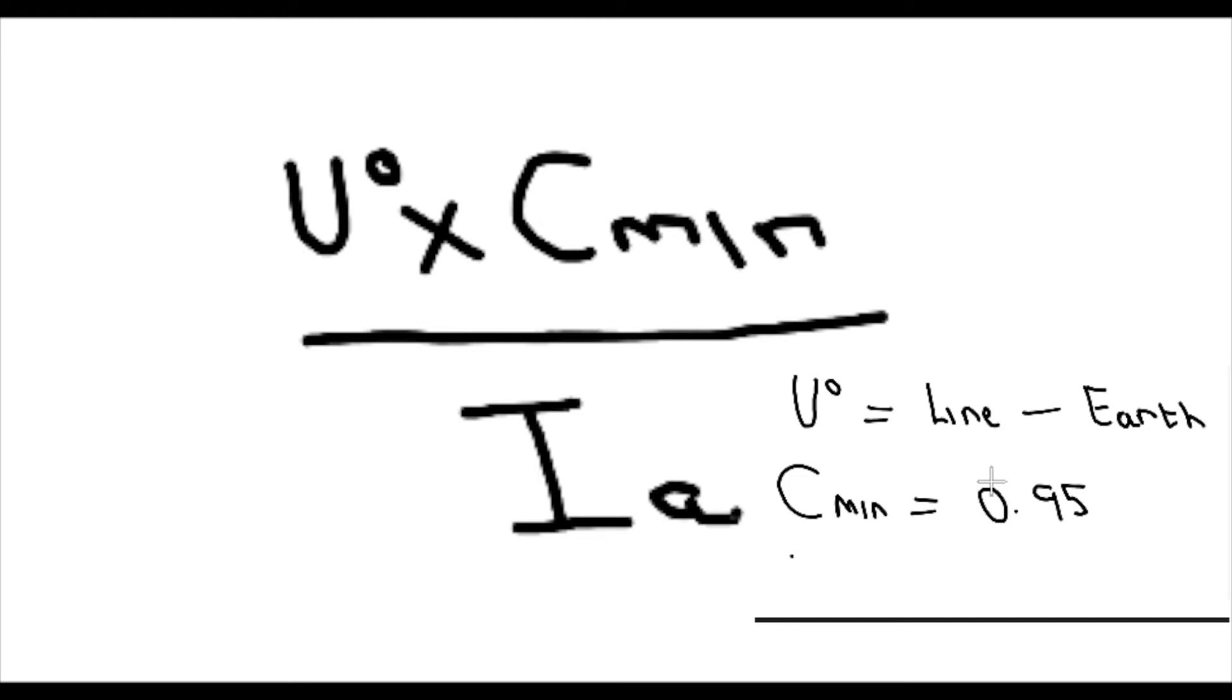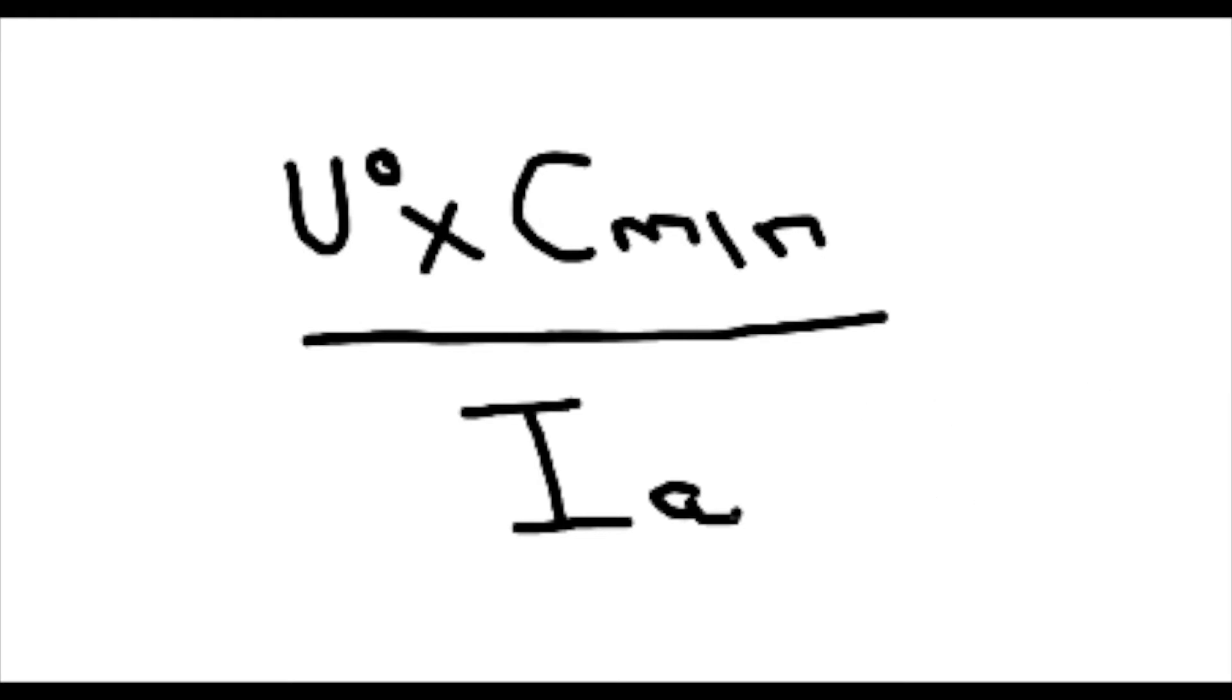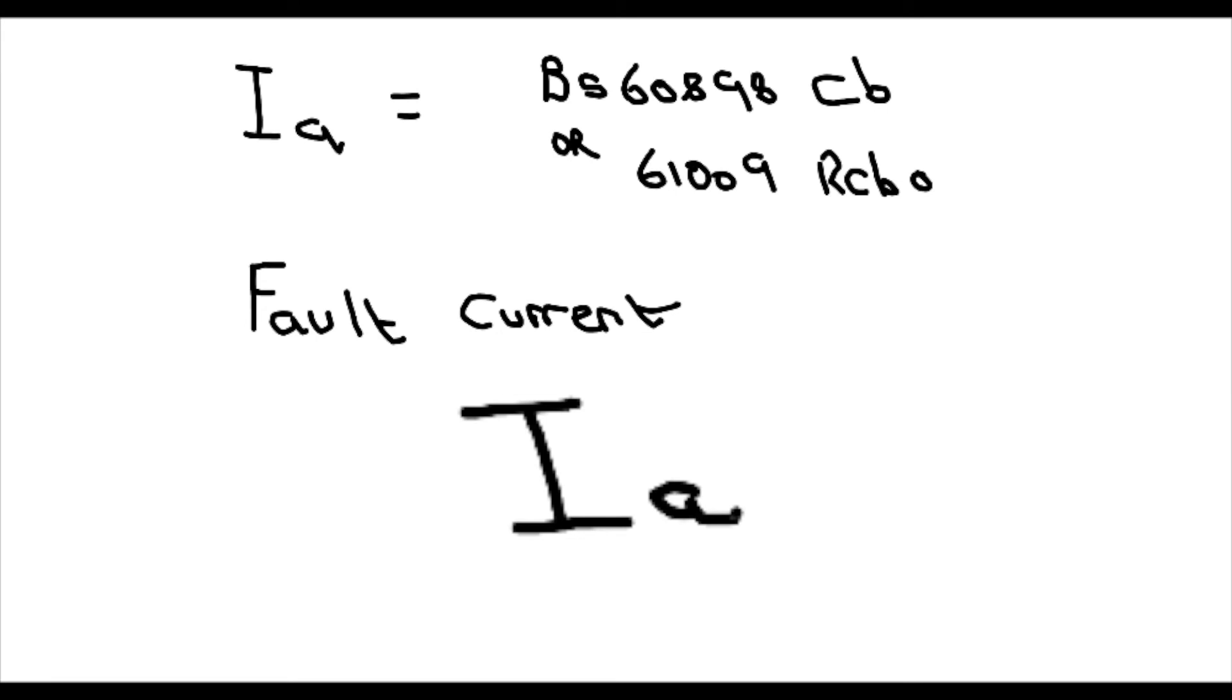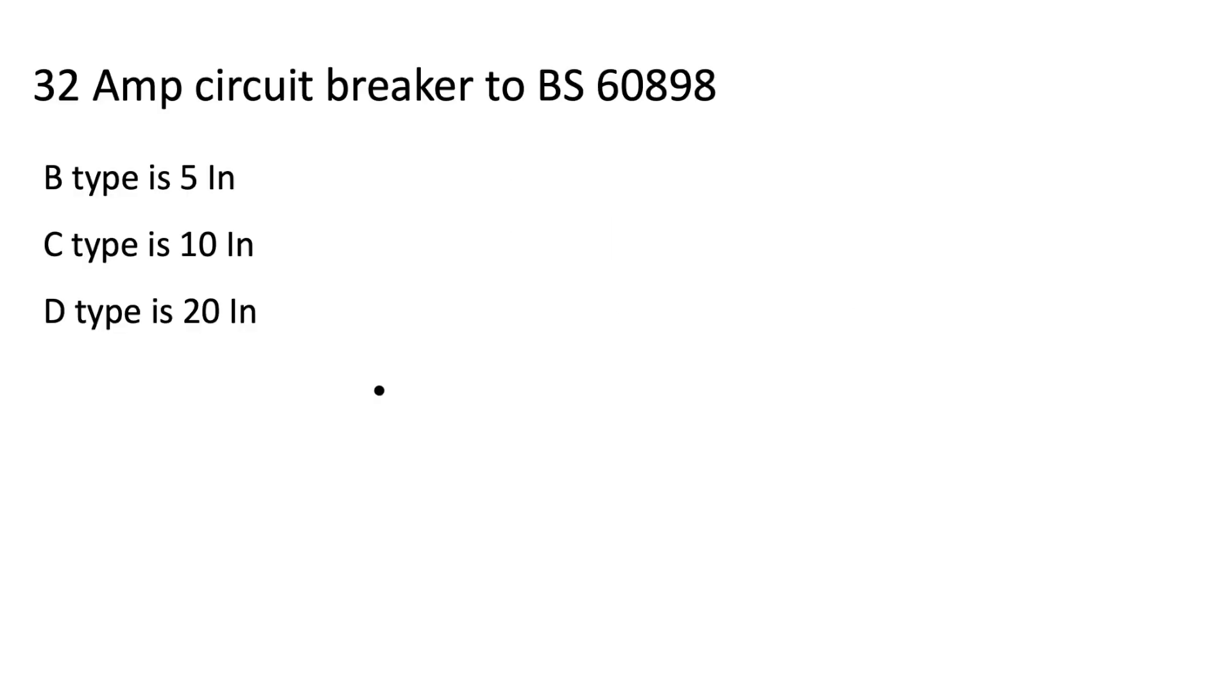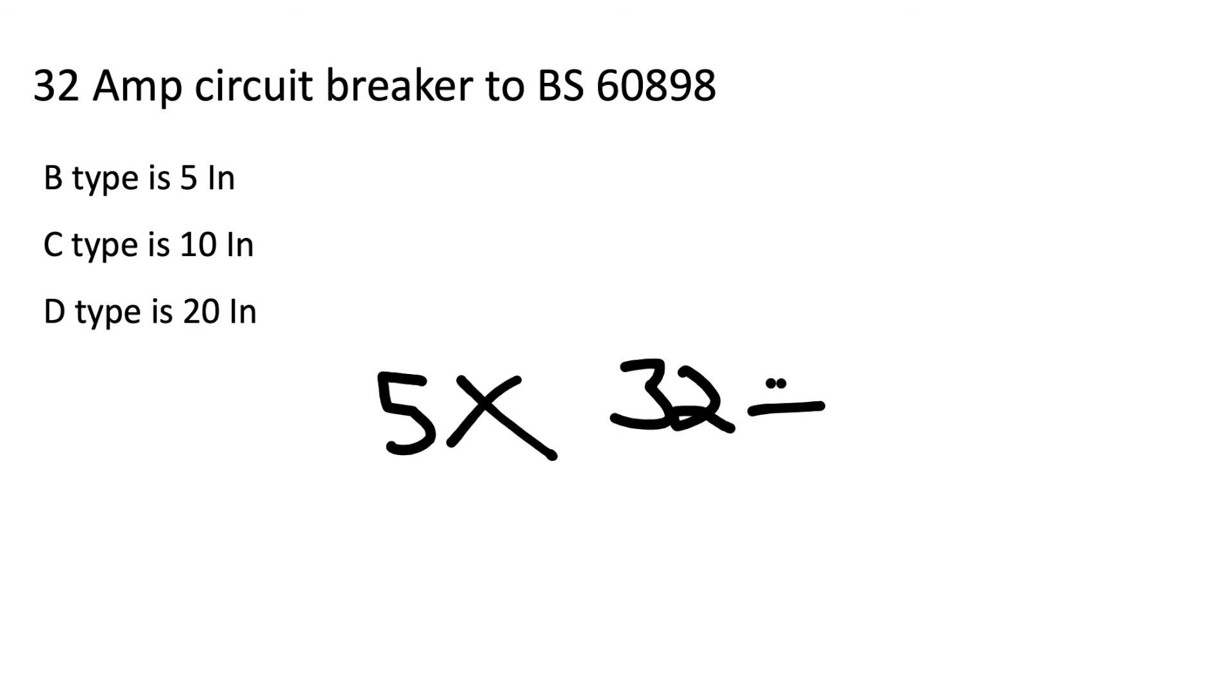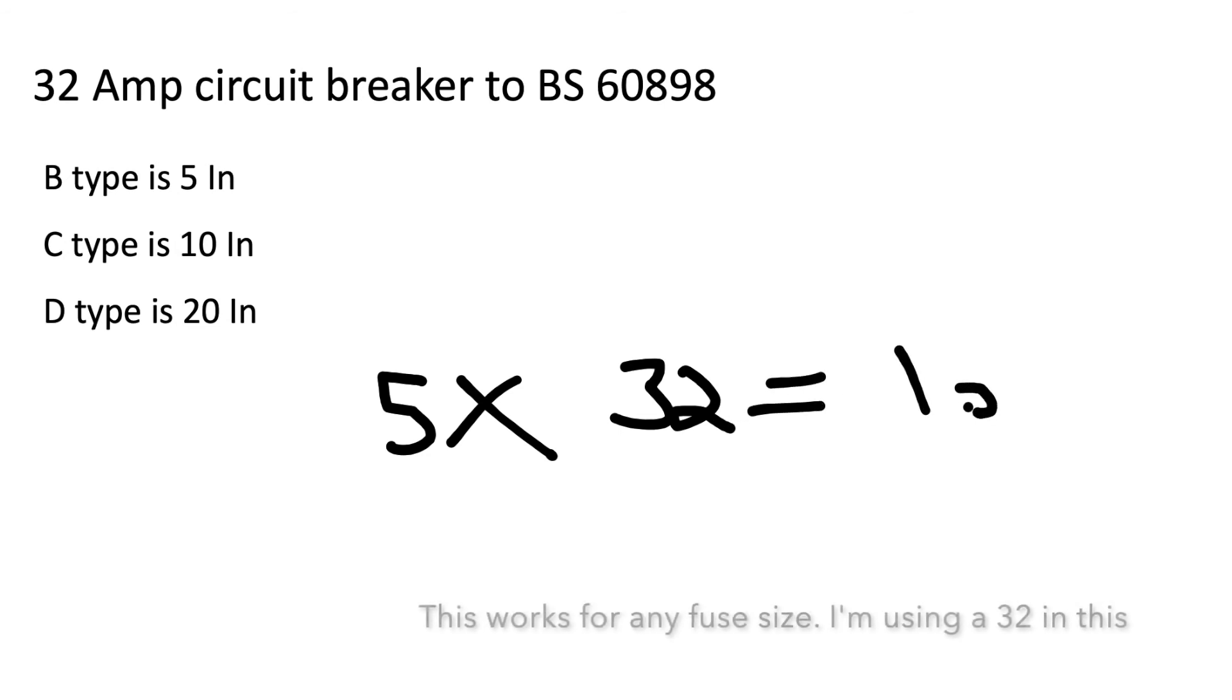C-Min is the correction factor I've just mentioned, which is 0.95. The I-A is from BS 60898 or 61009 - that's your circuit breakers or miniature circuit breakers and your RCBOs. What we need to find out is the actual fault current required to trip. Normally you'd have to look in your time current curves at the back of BS 7671, but we can actually work that out and I'm going to show you how.